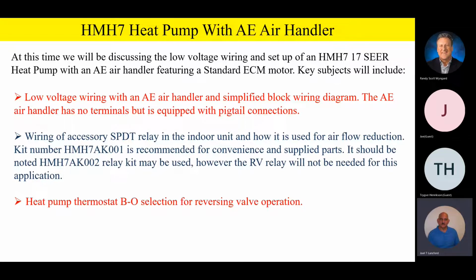Now, the obvious question is going to come up. A contractor may say, I've got my own bi-flow filter dryers, and I don't mind making up some field wiring of my own, and I've got a single pole double throw relay on my truck with a 24-volt coil. Can I use that instead? Well, of course you could. A single pole double throw relay with a 24-volt coil, a bi-flow filter dryer and field installed wiring would be perfectly acceptable. But for convenience, we recommend this kit because it comes with all that stuff in it already.